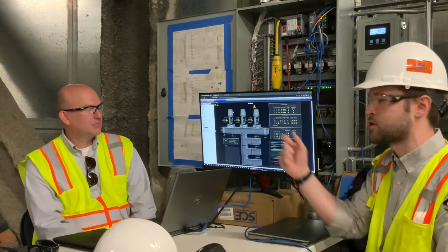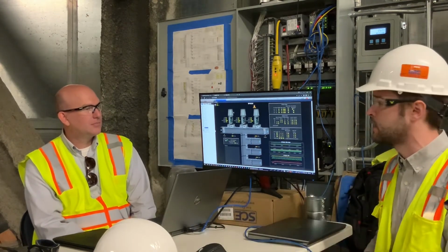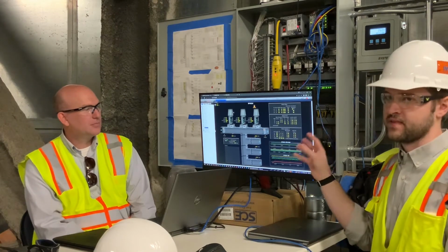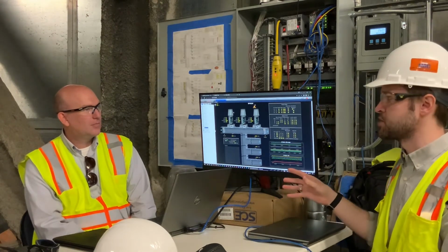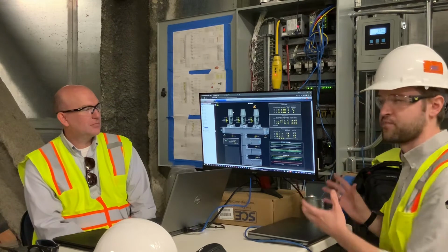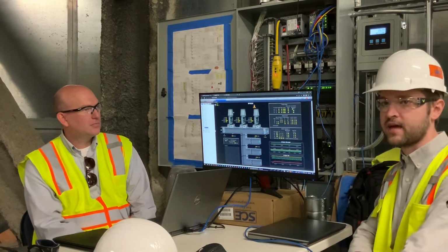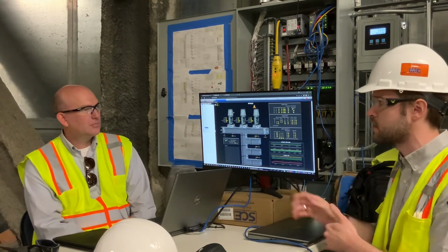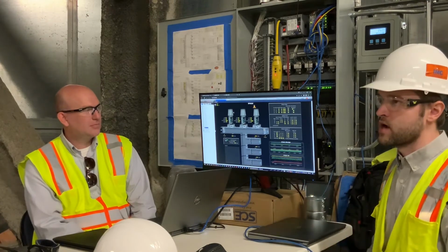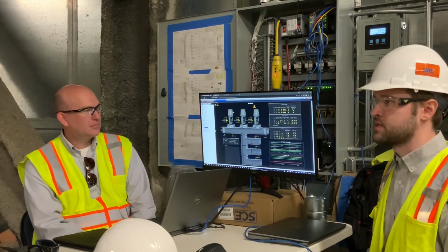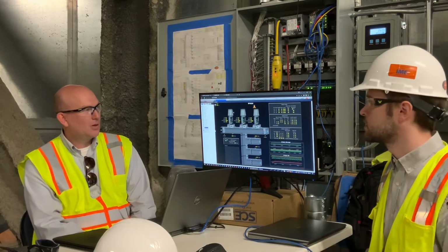I mean, you can turn the drive off. There's nothing wrong with doing that. But the program is going to think that fan has failed, rather than knowing you put it in maintenance mode. With maintenance mode, it's not even going to try with that fan. It'll continue operating otherwise. If you were to turn the drive off, it absolutely can do that, but it's just going to think that drive has failed.